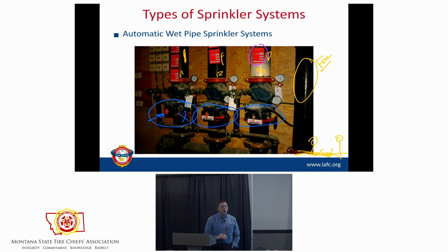So a couple things that we always need to tell people: when you shut off a riser, you shut off the smallest section, and once it's closed, you open up the main drain. All right? So in this case, this is a main drain, this is a main drain, this is a main drain. See this big valve right there? You would close that thing, or I know it's a little hard there, it's this guy right there. You close that, or you open that, and the water in all that pipe should go to an exterior or to the drain. All right?